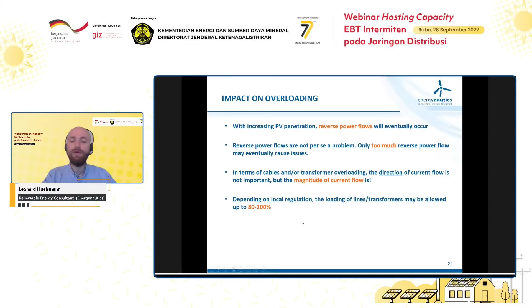Yeah, sounds good. Okay. So to explain here, you can have impacts on overloading. What happens with increasing PV penetration is that you will eventually have reverse power flows, which is actually not a problem by itself. Reverse power flow is not an issue itself. The only problem becomes if the reverse power flows become too much and distribution assets get overloaded. Usually, however, what you would allow is the loading of lines and transformers up to a level of 80 or maybe even 100%.